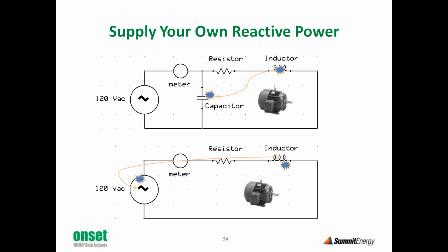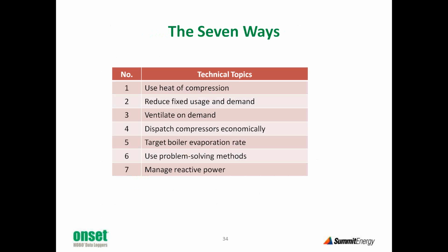Now it is true that there's a small additional savings associated with putting in your own capacitors. My recommendation is to ignore that if you're considering investing in power factor correction capacitors. Only buy them if they can be justified based on eliminating the penalties on your electric bill. I would not place a significant value on savings associated with line losses and other things. You may see material available from vendors indicating additional savings from capacitors. I would say that's icing on the cake, and that you should not use that to justify the investment.